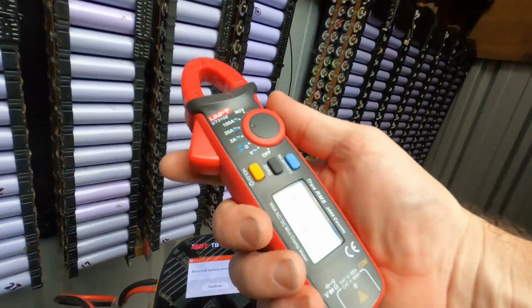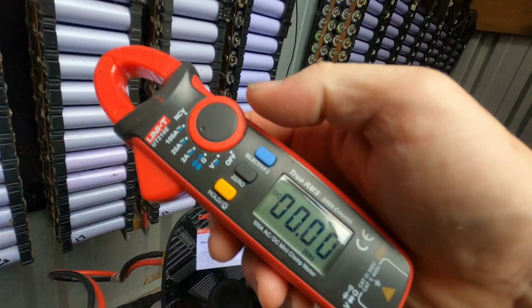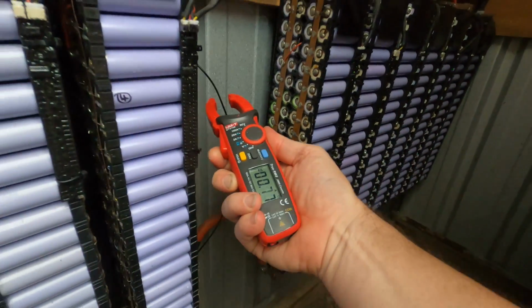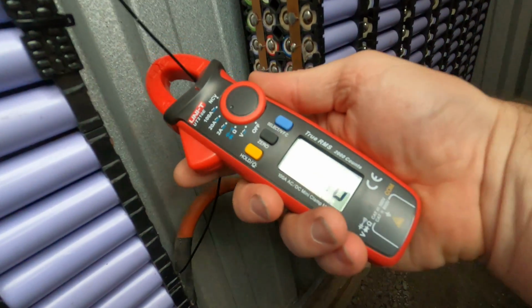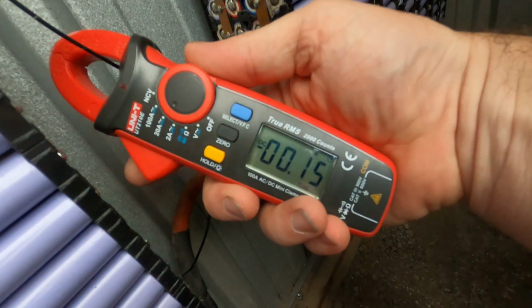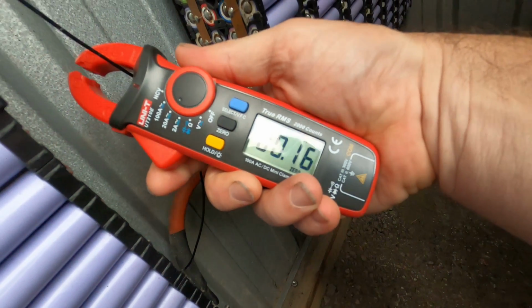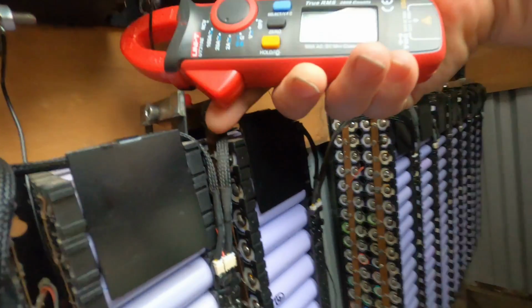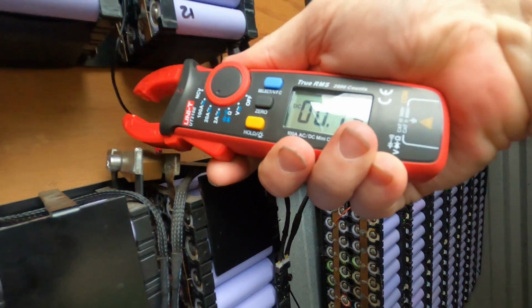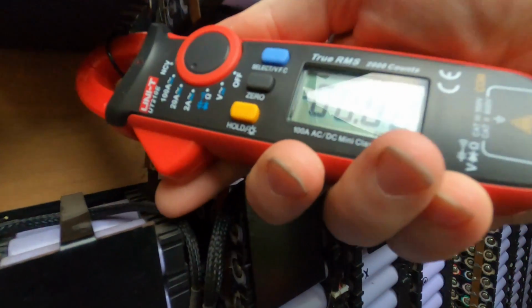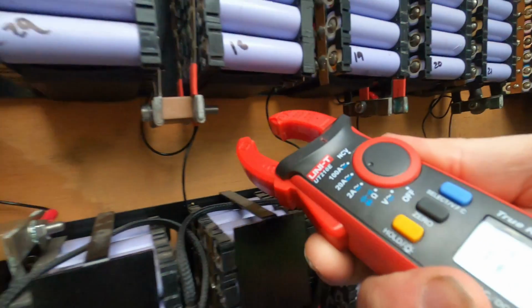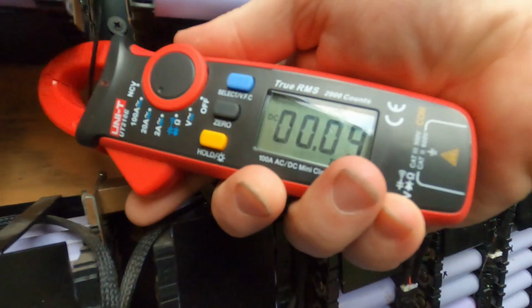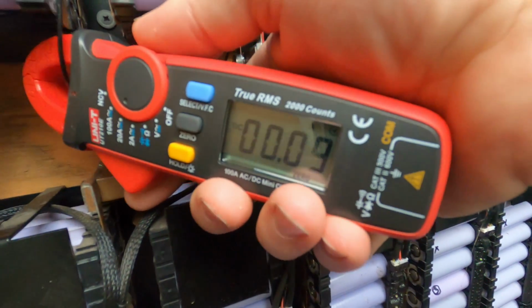I just turned it off beforehand because I want to get this little meter and then have a look at the balancing current between the batteries. And that's just saying 16 there. Oh, 0.16 of an amp. I'm seeing 0.14. I'll just do the easy ones.